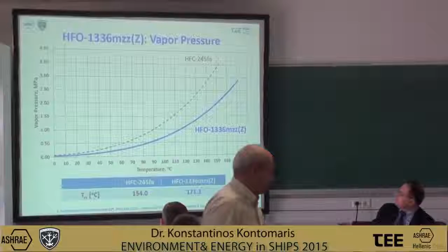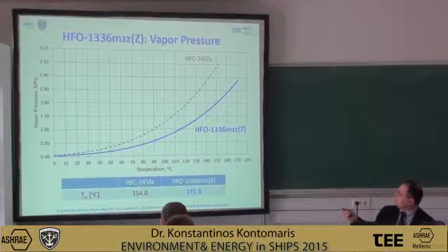This diagram shows you the vapor pressure of the two fluids of interest, the new fluid and the reference fluid. You can see that HFO 1336 generates significantly lower pressures, especially at high temperatures of operation. This is an advantage, as we will see soon.